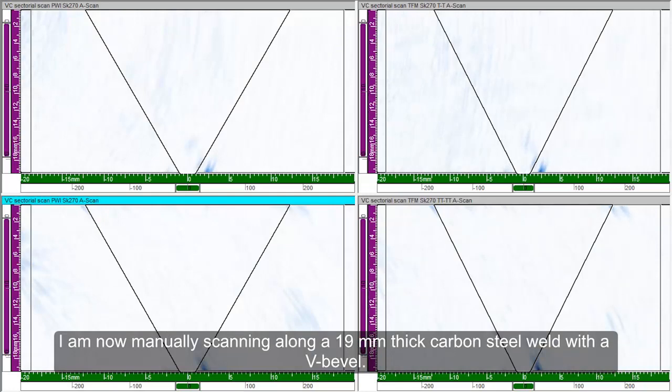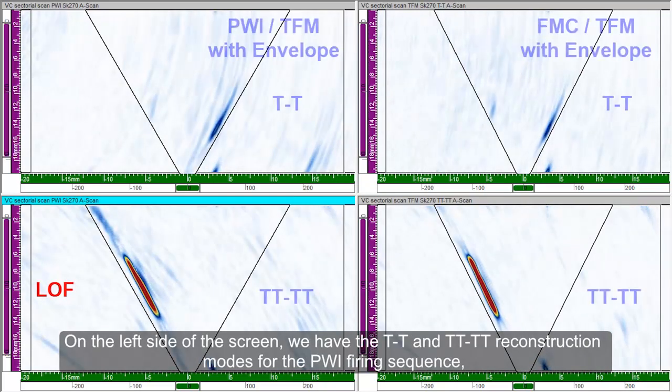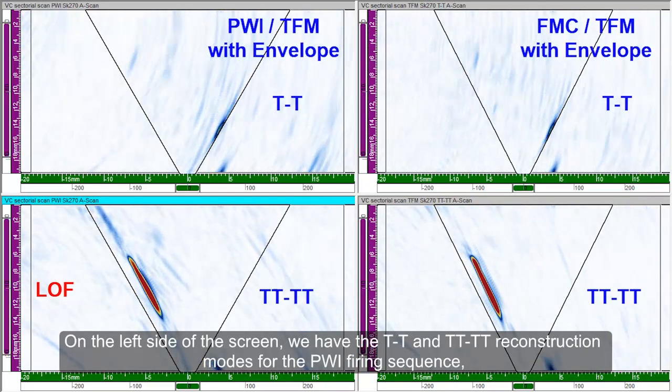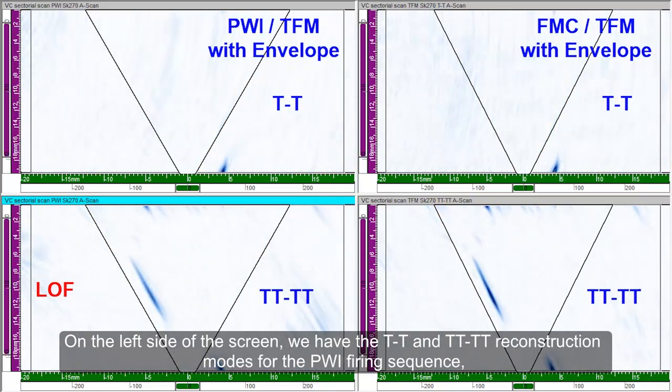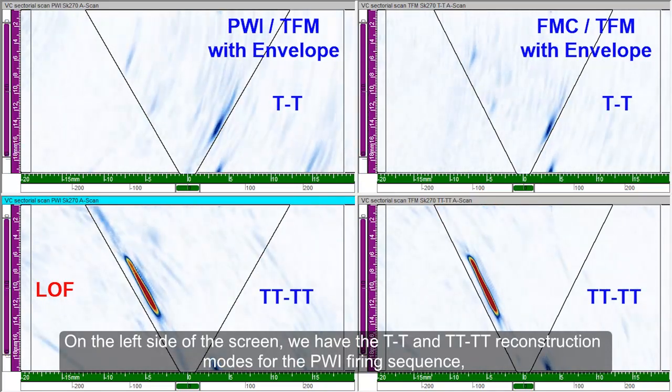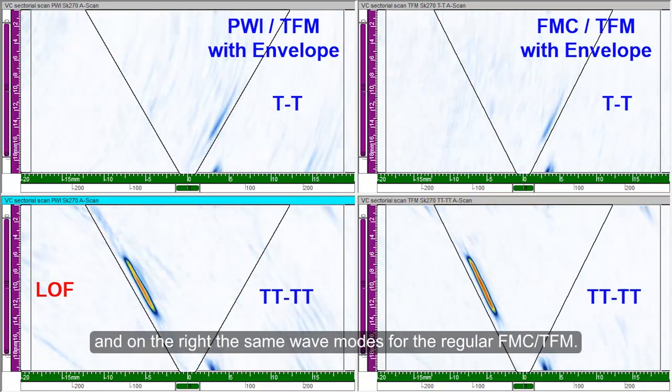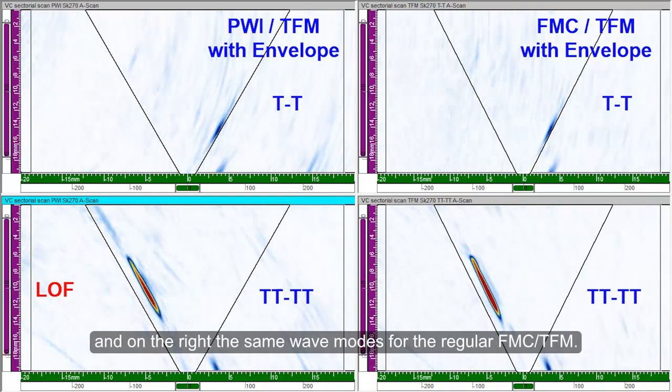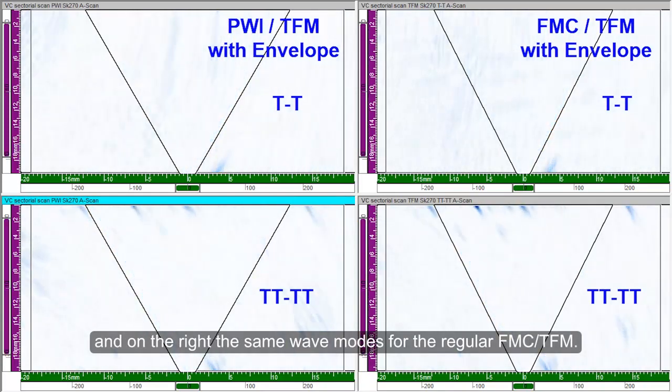I am now manually scanning along a 19 mm thick carbon steel weld with a V-bevel. On the left side of the screen, we have the T-T and TT-TT reconstruction modes for the PWI firing sequence. And on the right, the same wave modes for the regular FMC TFM.